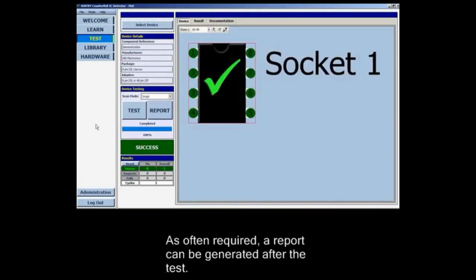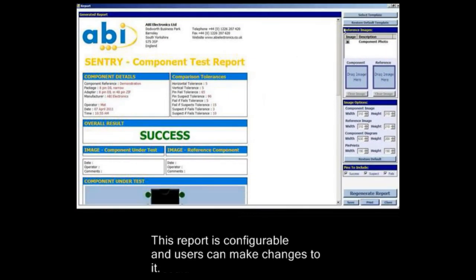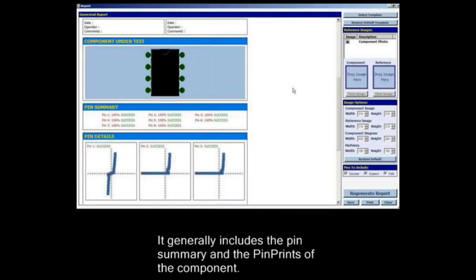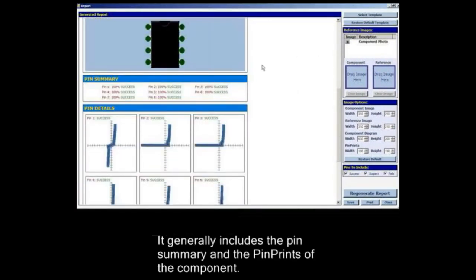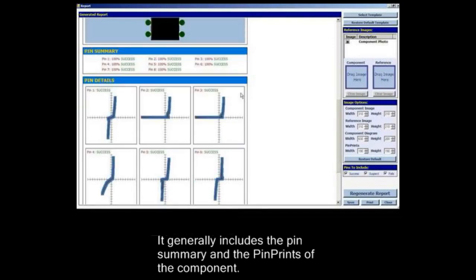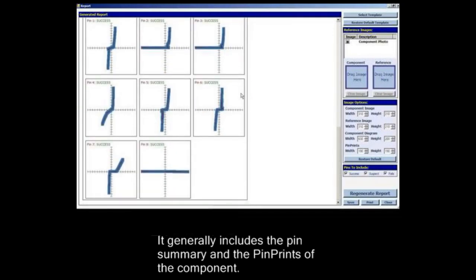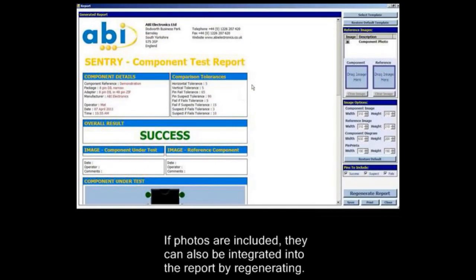As often required, a report can be generated after the test. This report is configurable and users can make changes to it. It generally includes the pin summary and also the pin prints of the component. If photos are included they can also be integrated into the report by regenerating.